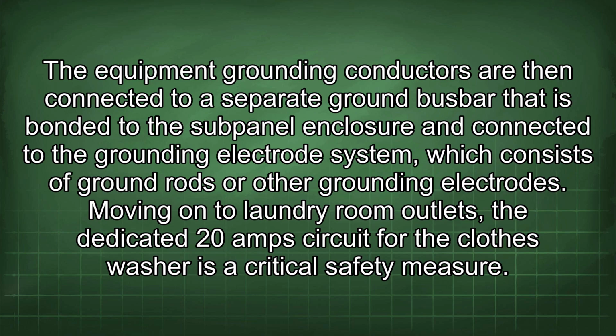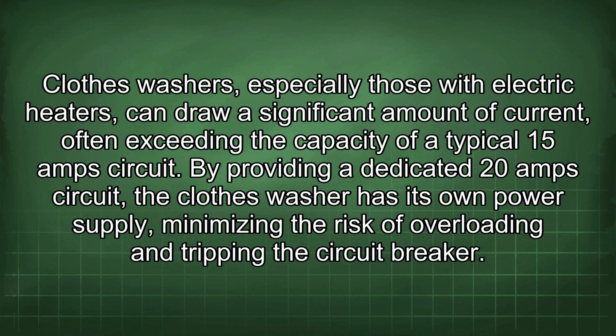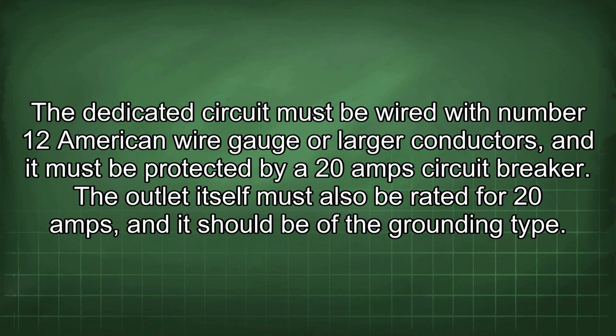Moving on to laundry room outlets, the dedicated 20 amp circuit for the clothes washer is a critical safety measure. Clothes washers, especially those with electric heaters, can draw a significant amount of current, often exceeding the capacity of a typical 15 amp circuit. By providing a dedicated 20 amp circuit, the clothes washer has its own power supply, minimizing the risk of overloading and tripping the circuit breaker. The dedicated circuit must be wired with number 12 American wire gauge or larger conductors, and it must be protected by a 20 amp circuit breaker. The outlet itself must also be rated for 20 amps, and it should be of the grounding type.